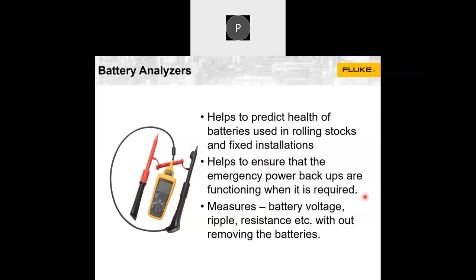Because of this, battery measurement is very important. It helps predict the health of batteries. When you have an array of batteries, maybe 10 or 15 in a bank, and one fails, the other batteries can get affected in no time. That's why you need periodic testing to ensure you're not spoiling the entire bunch of batteries, and to help ensure the emergency power backup is always functioning. When the emergency power backup isn't working, you'll be in the dark and your system will come to a complete stoppage.